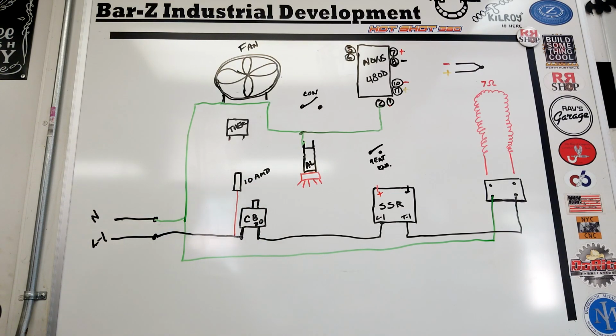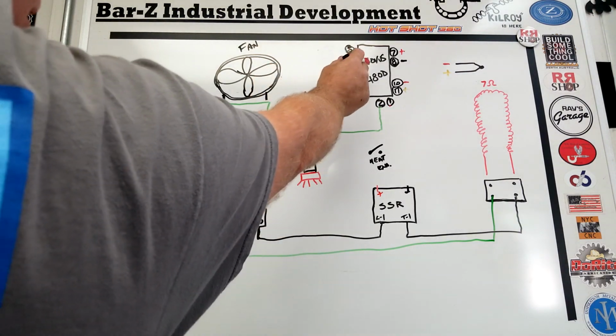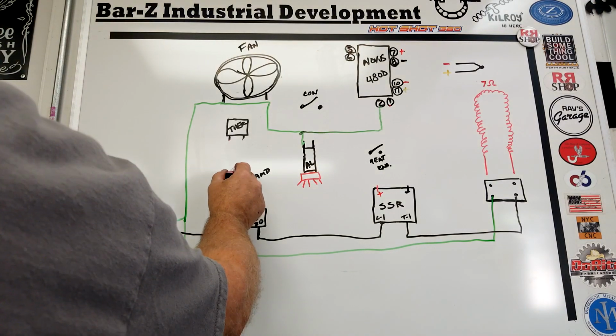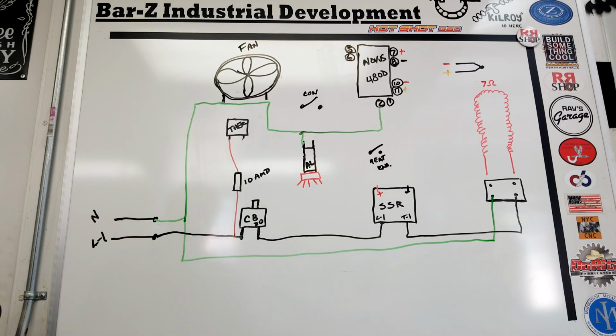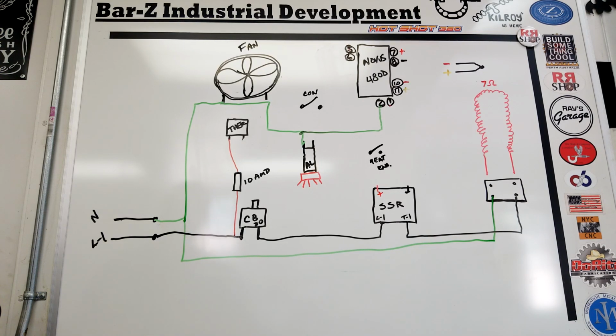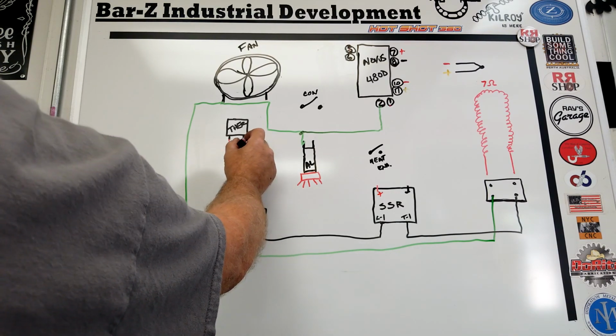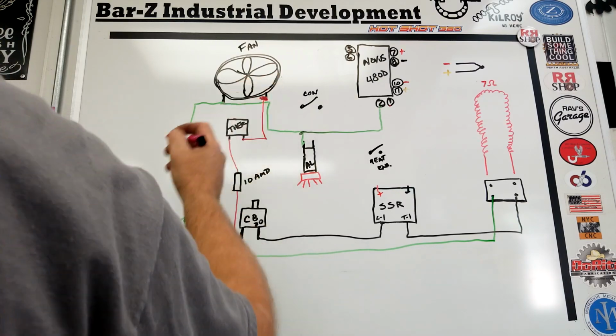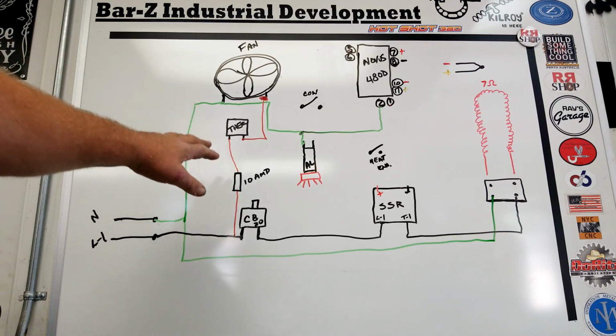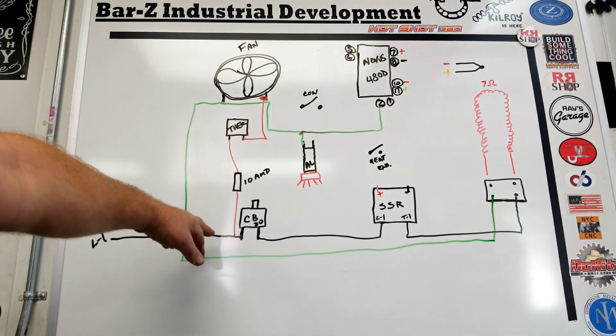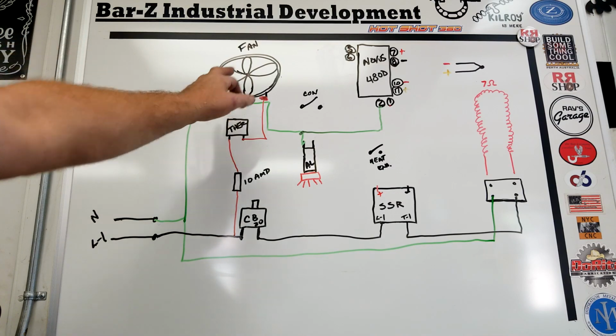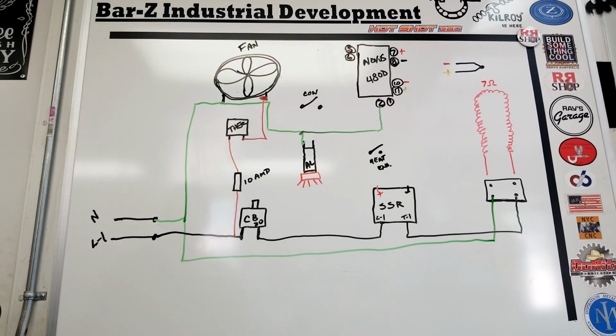All right. Out of that 10 amp breaker, that's your control fuse. That's just to protect the alarm, the fan, and the Novus. So you're going to come out of there. Very next thing you hit is a thermostatic switch. That's that little thermostatic switch that I showed you earlier. Okay. So out of there, we come out of that thermostat switch, we come out and we go up and we hit the other side of the fan. So at that point, that fan can run no matter what the rest of the oven's doing. That fan is capable of running and protecting the oven.